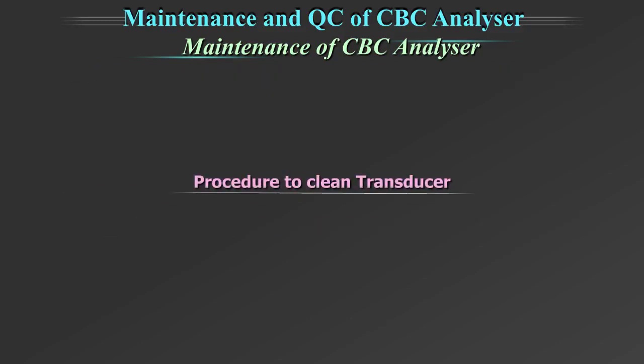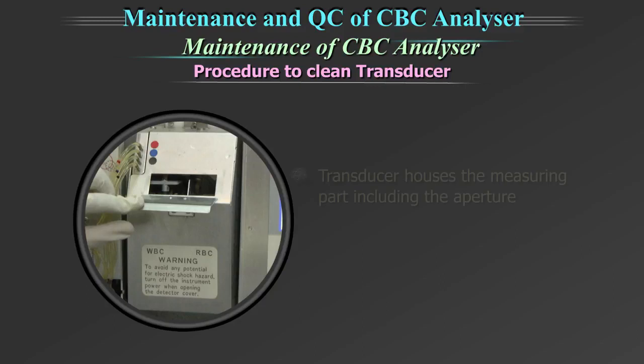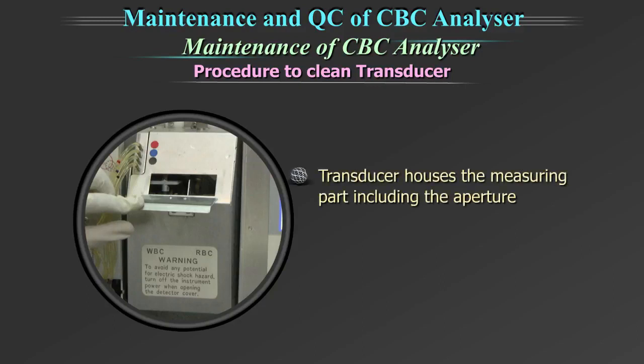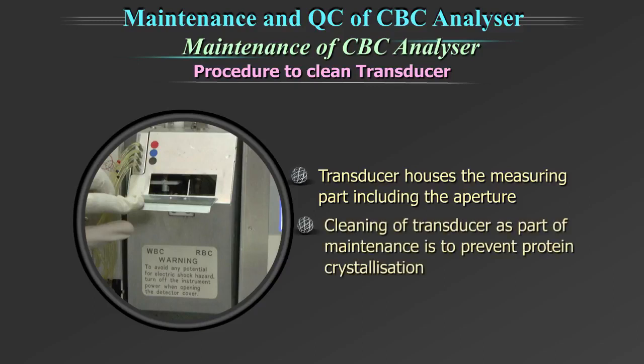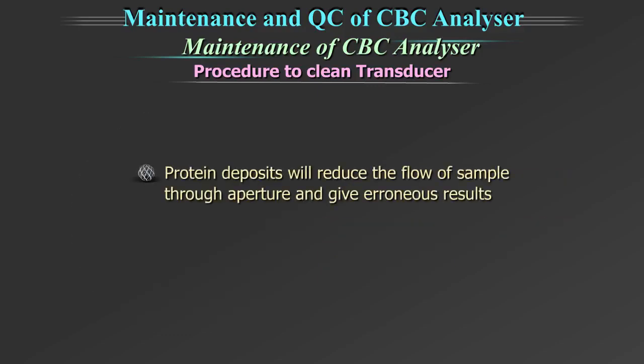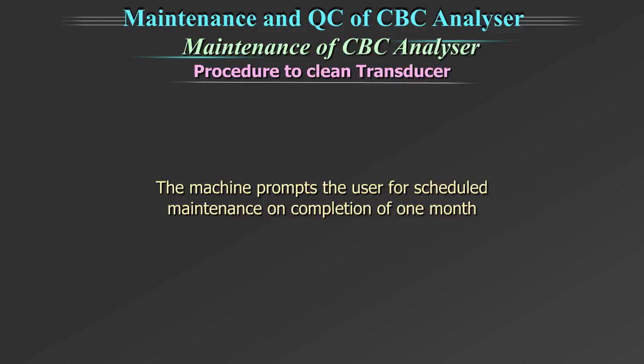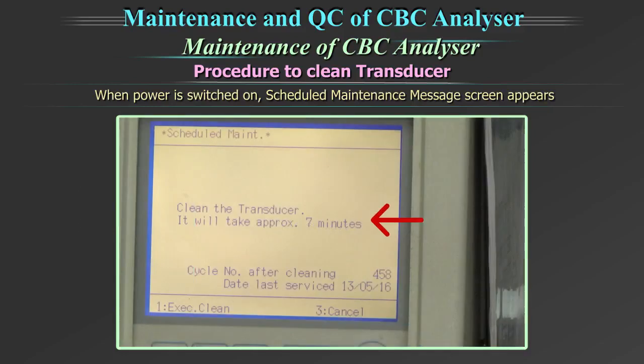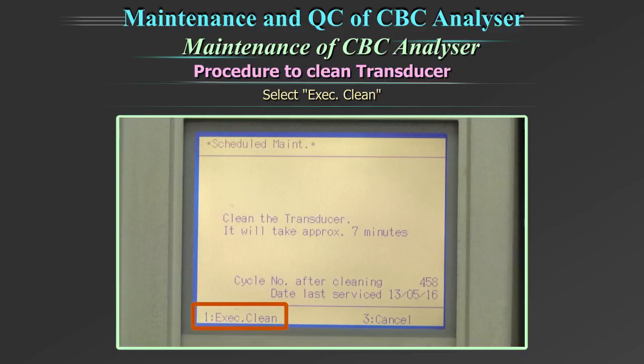Procedure to clean transducer. In this equipment, transducer houses the measuring part, including the aperture. The cleaning of transducer as part of maintenance is to prevent protein crystallization. Protein deposit will reduce the flow of sample through aperture to give erroneous results. This is a partially automated process. The machine prompts the user for scheduled maintenance on completion of 1 month. When power is switched on, scheduled maintenance message screen appears. Select the option Execute Clean.